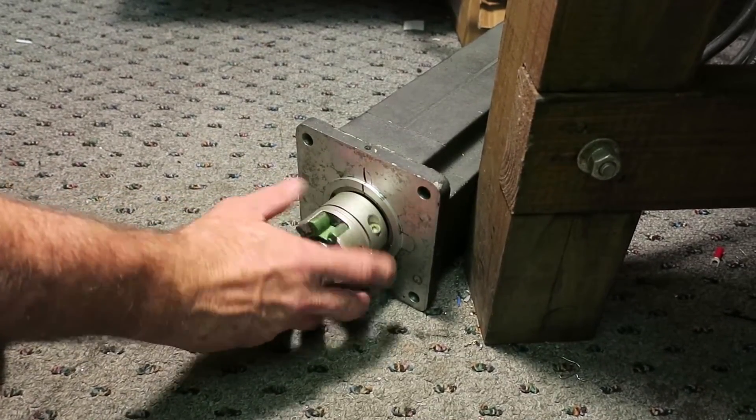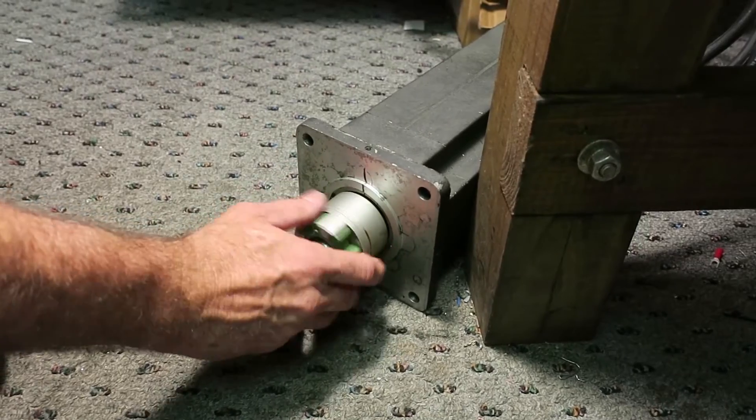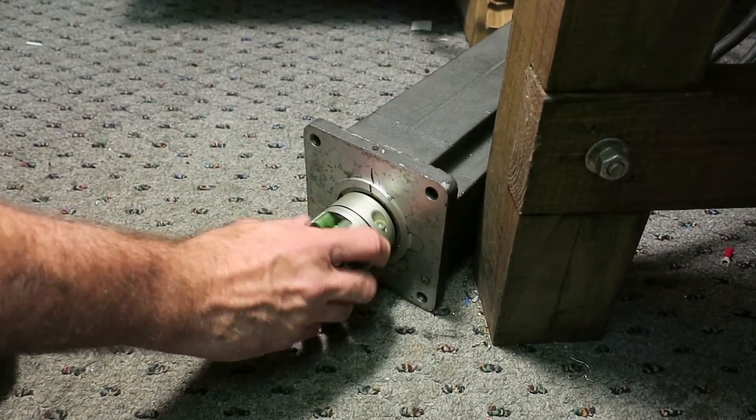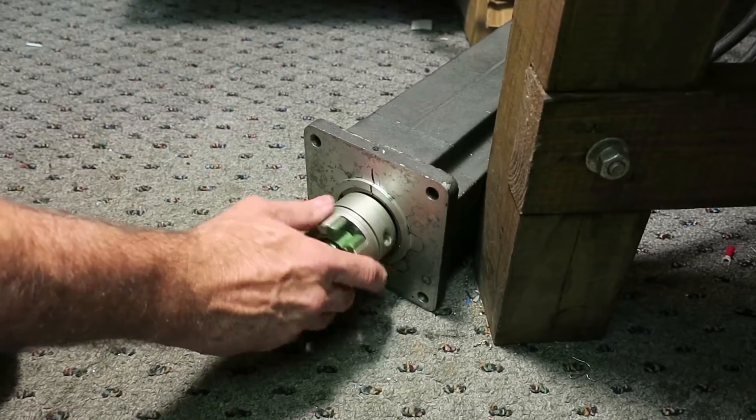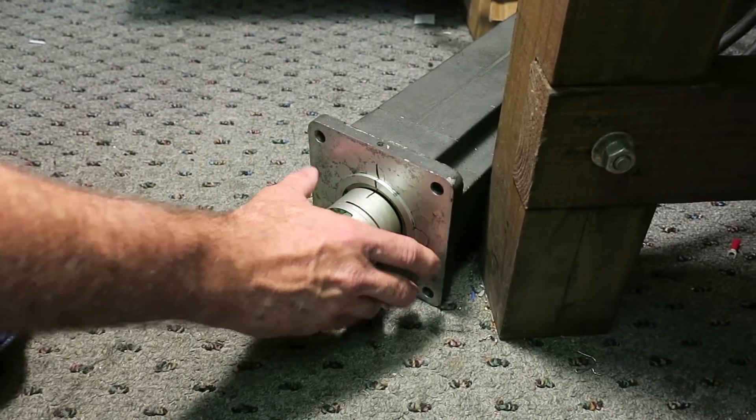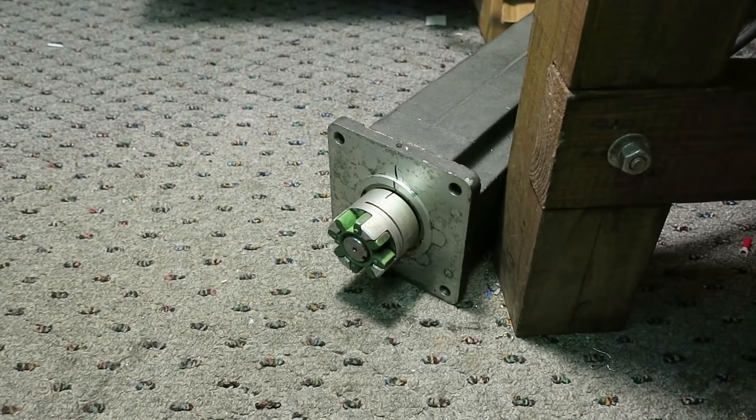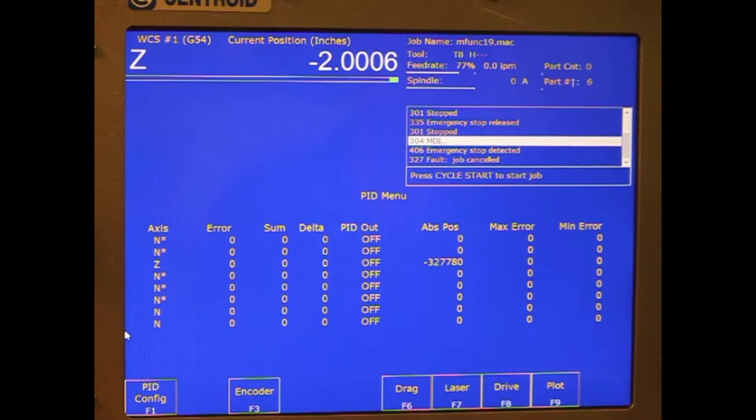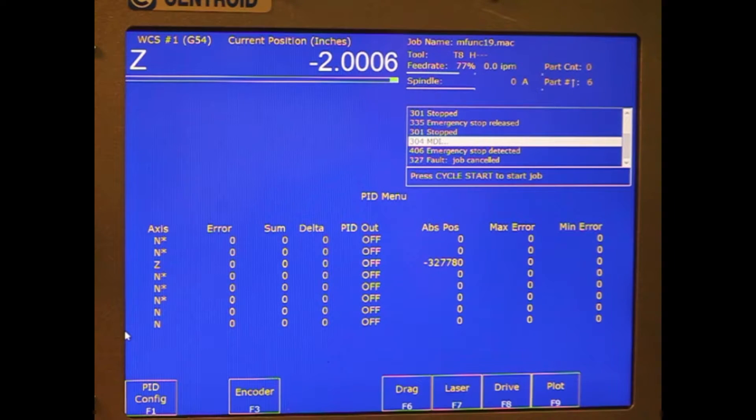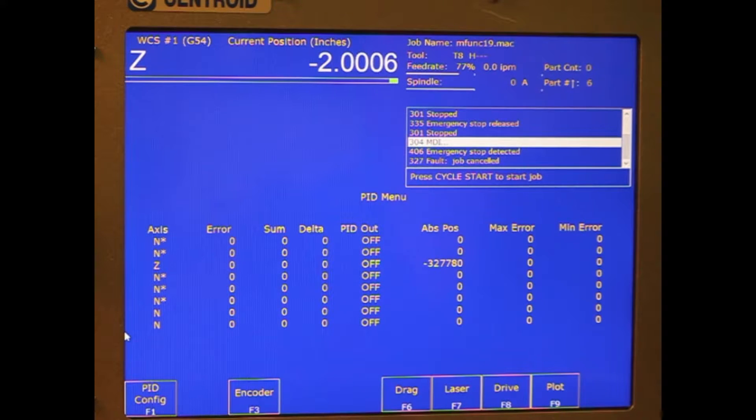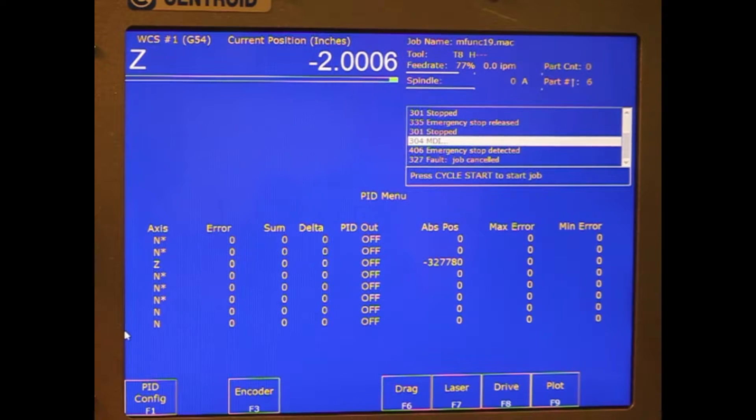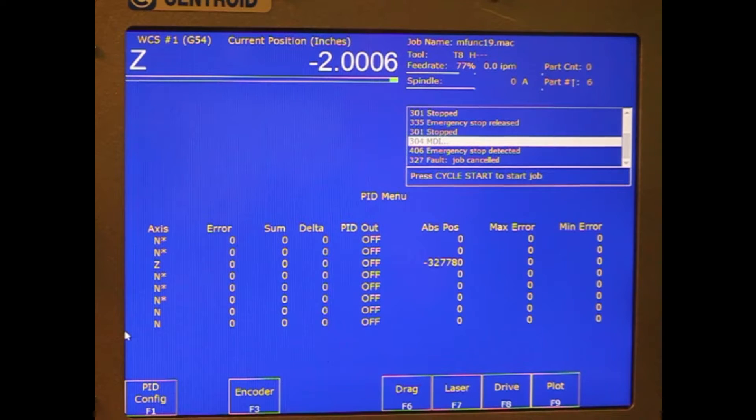Now we're going to go ten full revolutions and stop back on the mark. Now we're going to look at what number is in the ABS position. If you take that number, divide by ten, it'll tell you how many counts per revolution the encoder is. There's pretty much industry standards you'll be able to get close enough to tell which one it is.